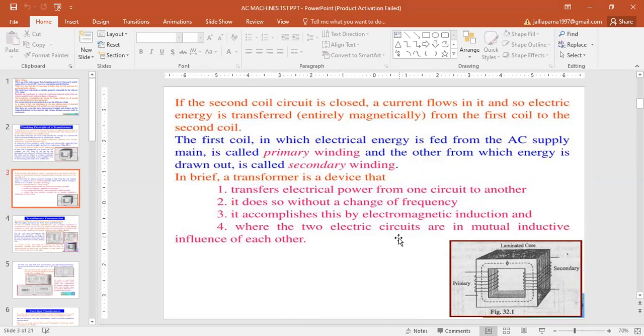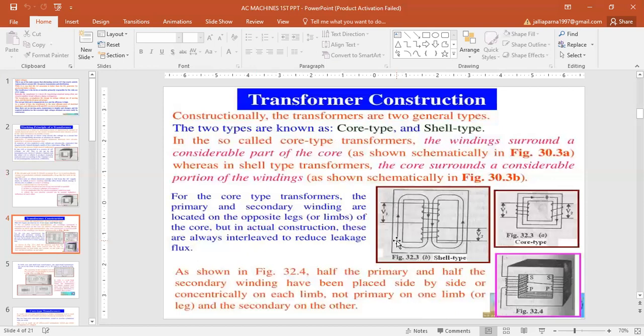Next one is transformer construction. Constructionally, transformers are of two general types, known as core type and shell type. In core type transformers, the winding surrounds a considerable part of the core, whereas in shell type transformers, the core surrounds a considerable portion of the windings. For the core type transformer, the primary and secondary windings are located on opposite legs, meaning limbs, of the core, but in actual construction these are always interleaved to reduce leakage flux. As shown in the figure, half of the primary and half of the secondary windings are placed side by side concentrically on each limb, not primary on one limb and secondary on the other.